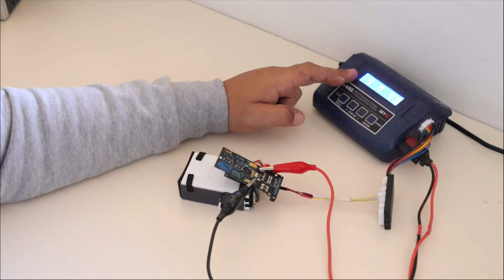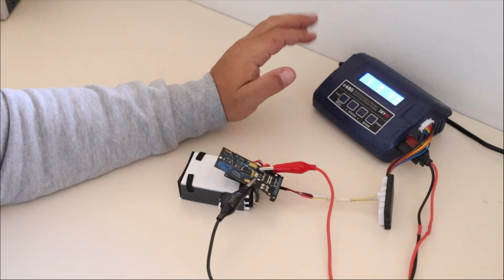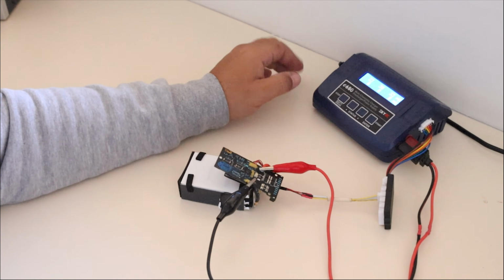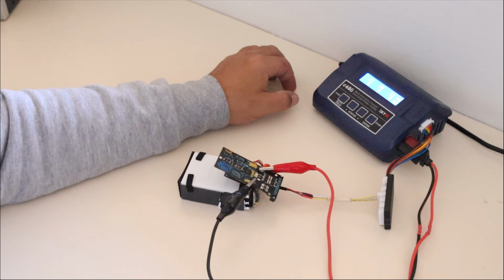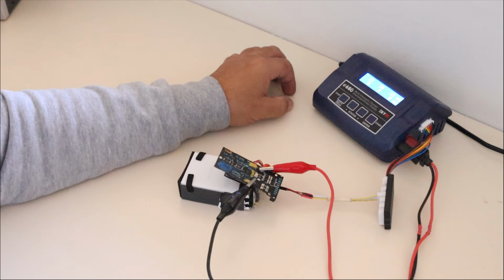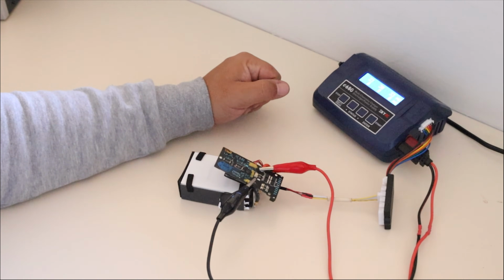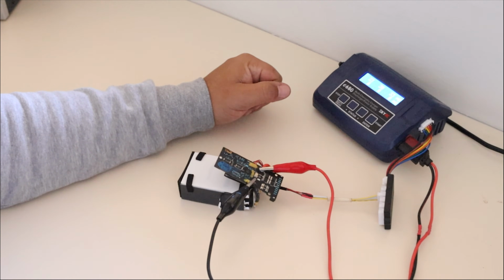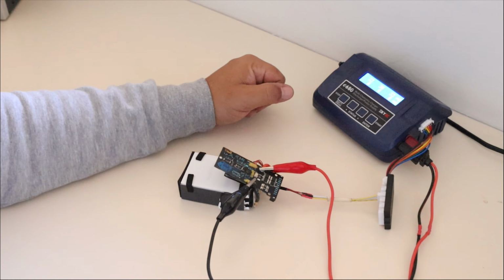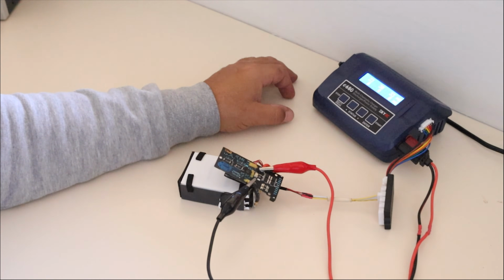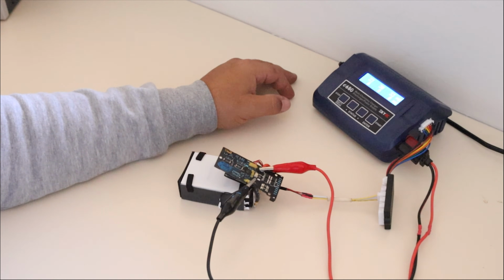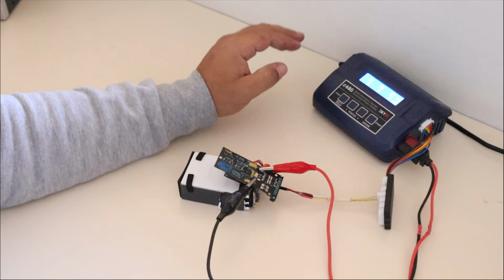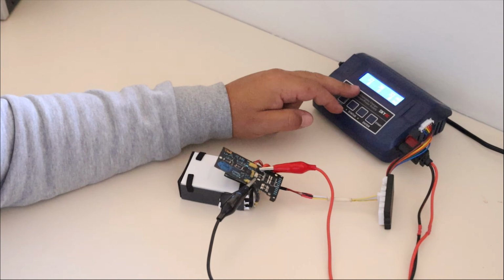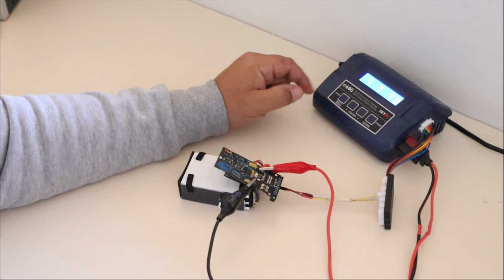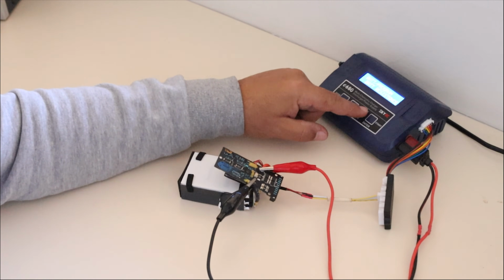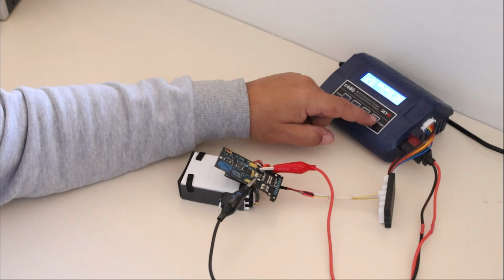Anything above 20, in my opinion, isn't necessarily dangerous, it's just that the higher resistance, the more heat it generates to charge and discharge. If you have a battery that shows 1, 5, 10, whatever the case may be in that range, that's a good battery - they tend to run a lot cooler than anything with high resistance. This battery will work, but it's not advised to use.